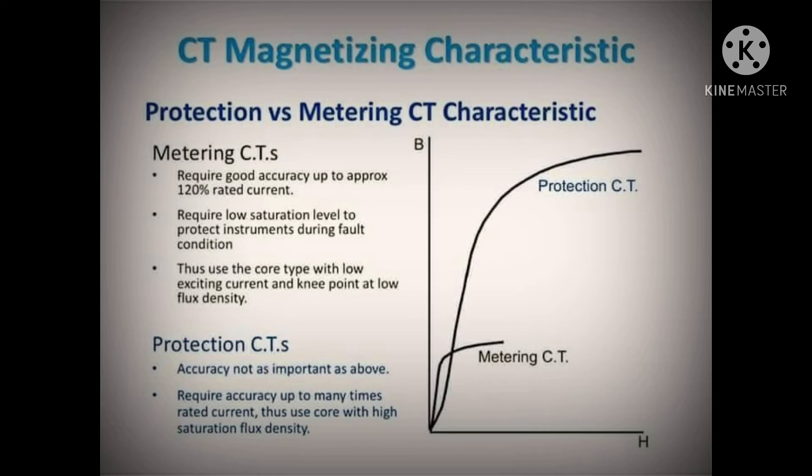Importance of CT saturation in differential protection schemes. The differential protection scheme is stable if it only trips on internal faults, or faults that happen within the zone of protection (ZOP), in between both CTs.